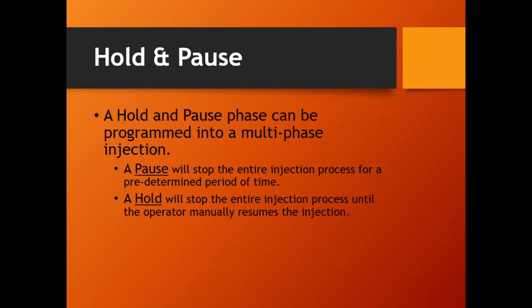Now, a couple other things. This is normally like a 2-hour presentation. I leave little things out, so here's a speed version of it. Now, there's other things that can be programmed into the phases. They don't all have to be injections. You can program a pause or a hold. No, they're not the same thing. If I program a hold, let's say in phase 2, a hold stops the injection, and it does not start again until the operator hits the button again. That's a hold. Now, a pause is the same thing, but it's for a predetermined length of time.